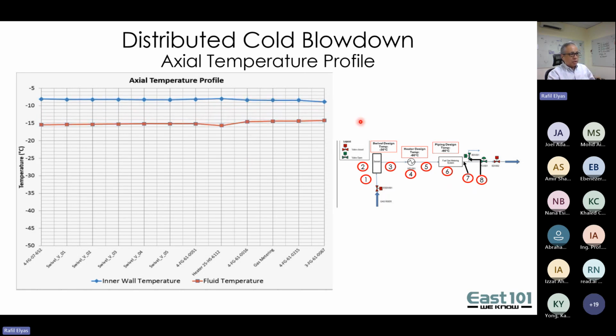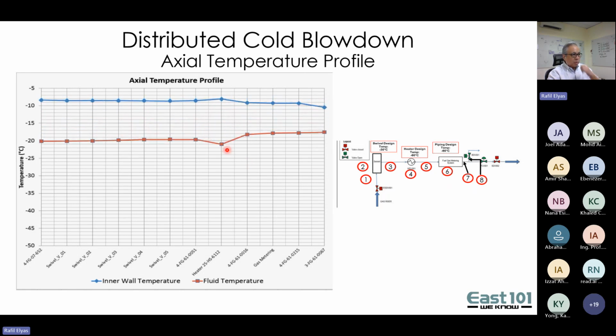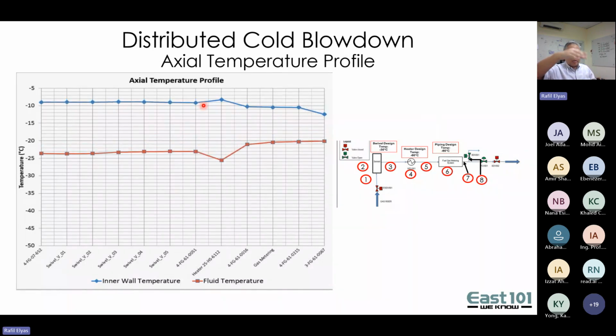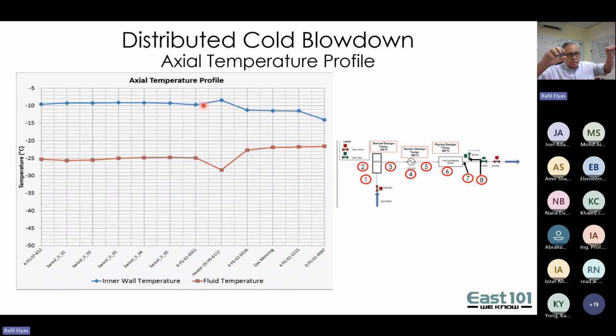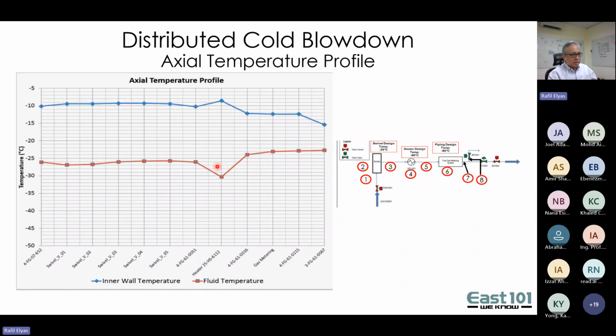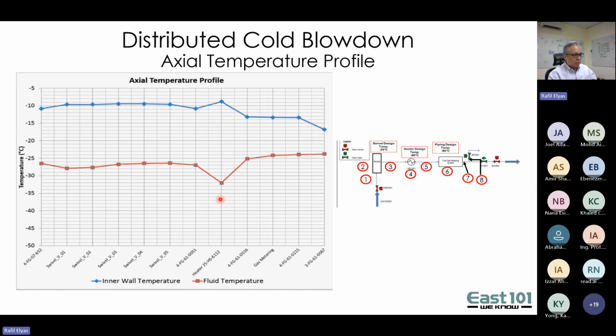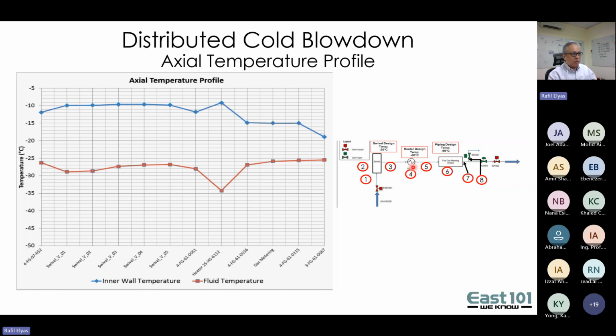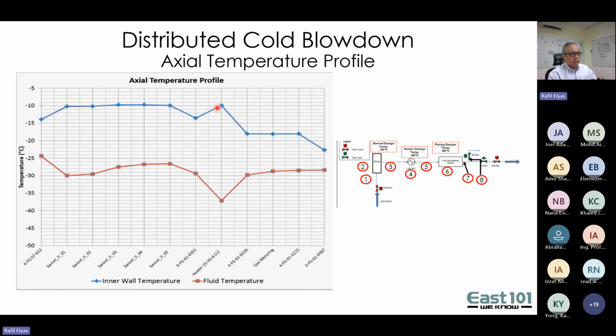So the depressuring starts. My liquid inventory temperature starts to drop, but the metal temperature still remains above because it's a thermal reservoir. It's still warm. You've got the heat capacity of the metal. And you find that this is the spot which looks like it's going down to about minus 41 at this point here. So this temperature is dropping to close to minus 40, but because there's a lot of metal mass around this point, because it's around the heater section, the inner wall temperature is still pretty high. I don't have any issues there. And I'm seeing that over here. I have enough thermal mass to prevent the temperature from dropping too low.